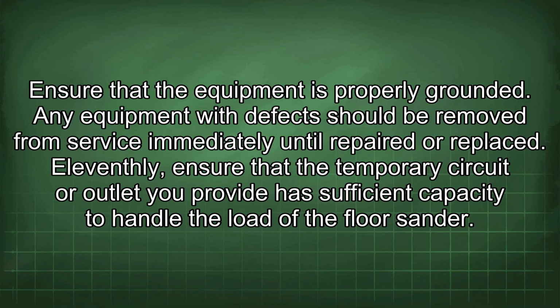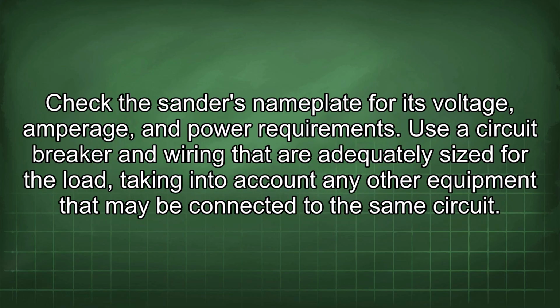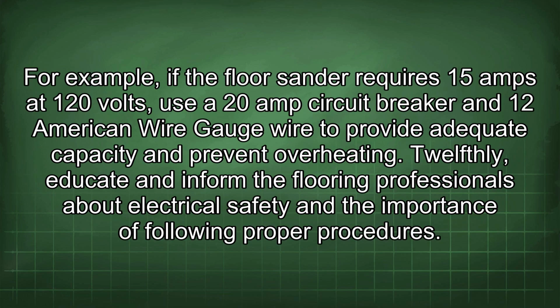Eleventhly, ensure that the temporary circuit or outlet you provide has sufficient capacity to handle the load of the floor sander. Check the sander's nameplate for its voltage, amperage, and power requirements. Use a circuit breaker and wiring that are adequately sized for the load, taking into account any other equipment that may be connected to the same circuit. For example, if the floor sander requires 15 amps at 120 volts, use a 20 amp circuit breaker and 12 American wire gauge wire to provide adequate capacity and prevent overheating.